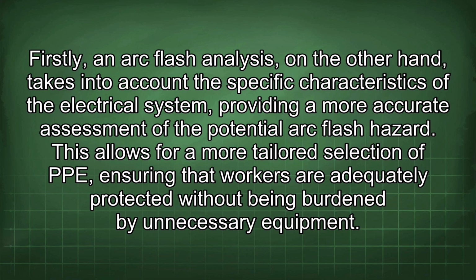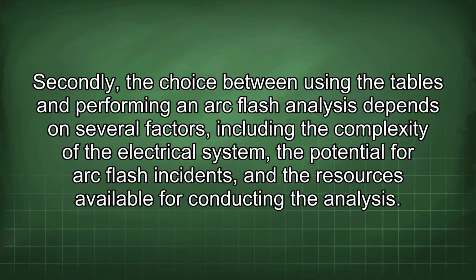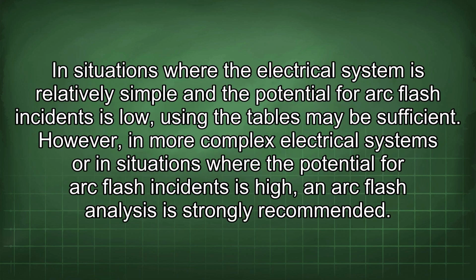This allows for a more tailored selection of PPE, ensuring that workers are adequately protected without being burdened by unnecessary equipment. Secondly, the choice between using the tables and performing an arc flash analysis depends on several factors, including the complexity of the electrical system, the potential for arc flash incidents, and the resources available for conducting the analysis. In situations where the electrical system is relatively simple and the potential for arc flash incidents is low, using the tables may be sufficient. However, in more complex electrical systems or in situations where the potential for arc flash incidents is high, an arc flash analysis is strongly recommended.